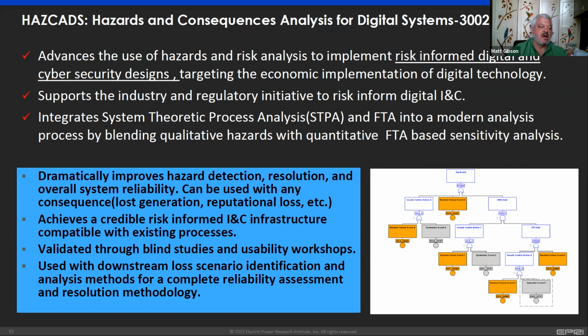Ultimately, we can also put these in as basic events in your fault trees. We're not measuring what I would call the assessment risk. What we're doing is measuring the sensitivity. Why? Because the insight you're looking for is to know what design features you need to put in based on this risk sensitivity of your design. So that's the risk-informed element here.